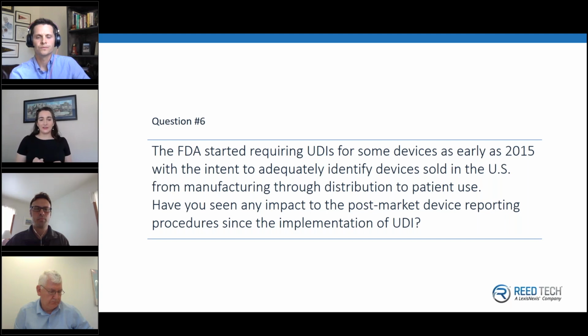There isn't a designated field on the recall report or the adverse events, and definitely not in the user interfaces. So when you look at a recall that might have UDIs listed on them, they're all kind of in a big chunk of text. Sometimes they're separated by a space, sometimes by a comma, sometimes by a semicolon. So it's kind of hard to recognize them, and sometimes they're just submitted in the same field along with catalog numbers and other manufacturer identifiers.